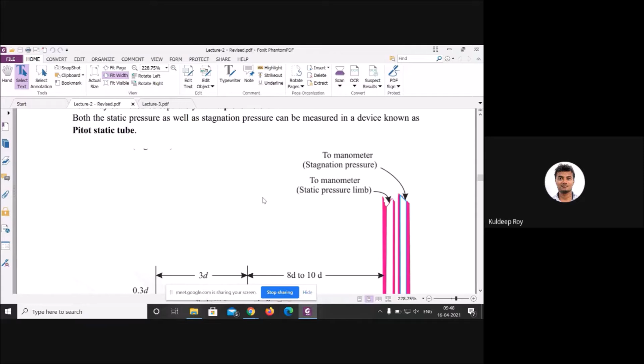If you are looking for a static pressure, then you have to apply one hole. Now you can see, static hole means that through this hole, when the fluid flows from this position to this position, it will show some kind of static pressure. If you are looking for dynamic pressure, V square by 2g, then you have to subtract static pressure from stagnant pressure, and you will get the dynamic pressure. If you get the dynamic pressure, you can easily determine your velocity. Okay, same formula.